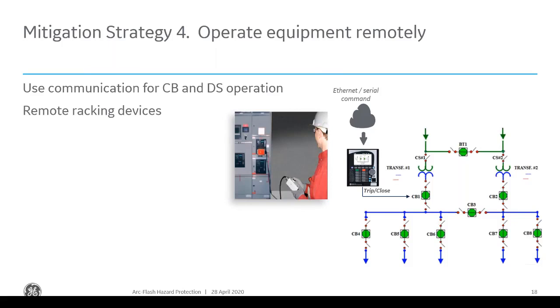Remote racking devices. This is also part of the options in certain switchgear, especially low voltage switchgear these days, because you might not have remote communication to every piece of your low voltage switchgear. So you can have these remote racking devices. You can see this guy has a little lead that he plugs into the control, and then he stays far away to be able to operate it.